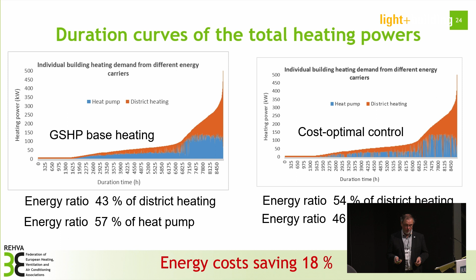Coming back to the conclusion, I think it is quite obvious that buildings need to be more energy flexible, because energy production is based on renewable energies. From a Scandinavian point of view, wind energy is becoming more and more important in wintertime, and in the future it is estimated that a major part of our heating will be based on renewables. That means we have to take measures in buildings too, and demand response is one option. Based on this analysis, we can see a range of 6 to 23% cost savings when utilizing the dynamic energy price and also cutting the power demand. So a big part of the saving comes from reducing the power needed in the building.